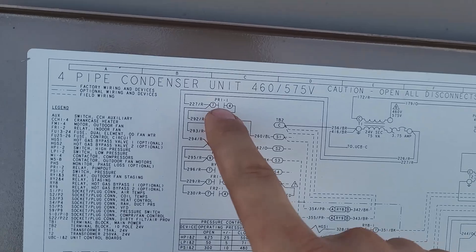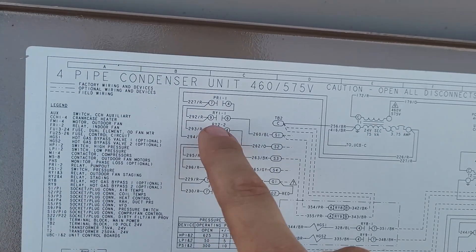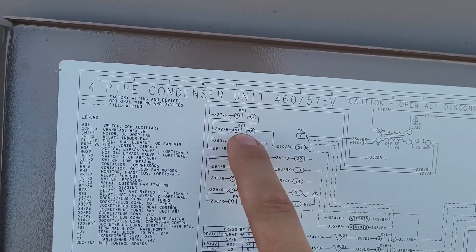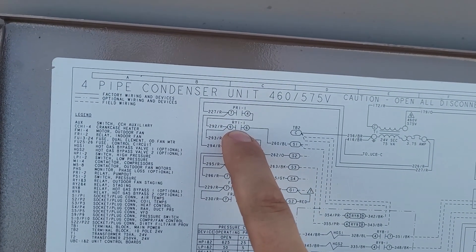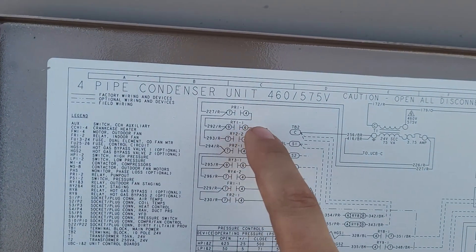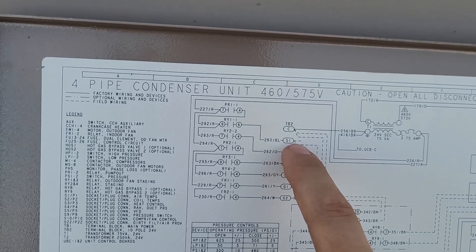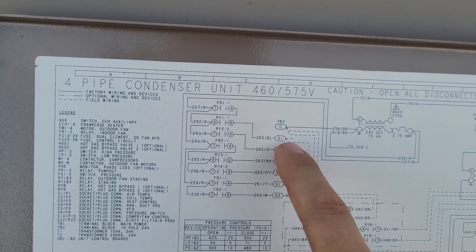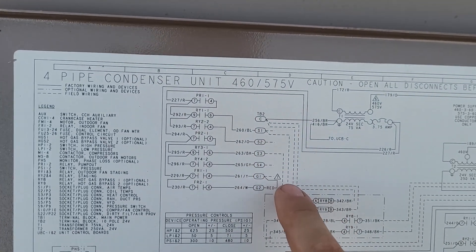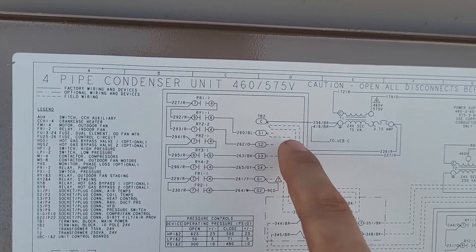So the pump-out relay can feed the RY1 relay, which can back-feed 24 volts down to my thermostat.